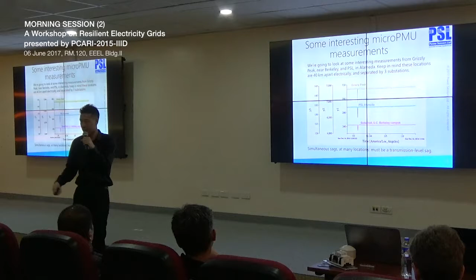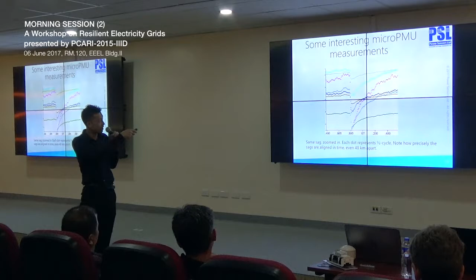These 3 locations are separated electrically by 40 kilometers and 3 substations in between. If you look here, you can see the voltage dip occurred on all 3 units, so we know the voltage disturbance originated on the transmission level. Zooming in, you can see just how well aligned the voltage dips are.